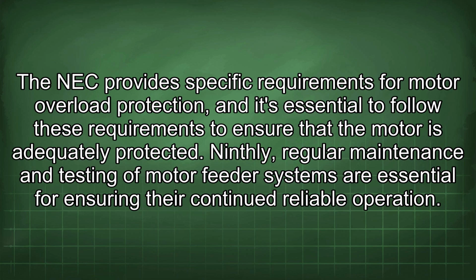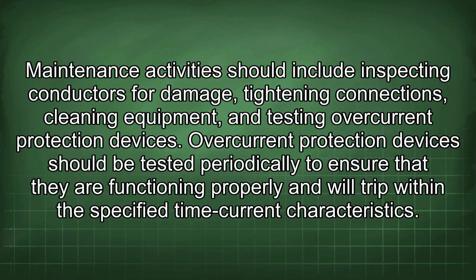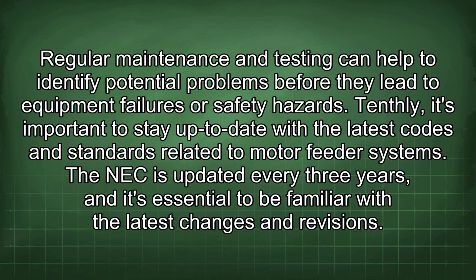motor is adequately protected. Ninthly, regular maintenance and testing of motor feeder systems are essential for ensuring their continued reliable operation. Maintenance activities should include inspecting conductors for damage, tightening connections, cleaning equipment, and testing overcurrent protection devices. Overcurrent protection devices should be tested periodically to ensure that they are functioning properly and will trip within the specified time current characteristics.